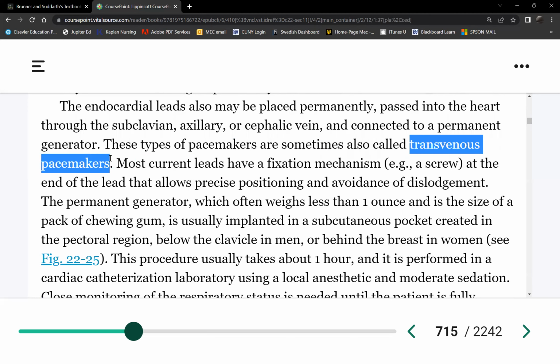Transvenous means this is a type of temporary pacemaker wherein the pacemaker is outside the body. It's handheld. However, the wires are inside the patient's body. I'll explain why someone would require a pacemaker like this shortly. And the fastest way to pace somebody is through an external pacemaker. So all defibrillator machines are also external pacemakers. Okay, they are also temporary pacemakers.